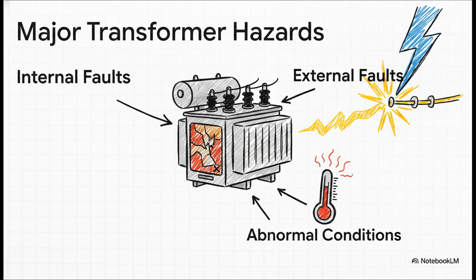First up, you've got internal faults. These are problems brewing deep inside the guts of the transformer, in its windings or its core. Then you have external faults, like a short circuit happening way down the line that sends a massive destructive surge of electricity racing back toward it. And finally, there are just abnormal conditions. You can think of this like the transformer getting a fever, maybe from too much voltage or just plain overheating. If you don't catch any of these, you're looking at fires, explosions, and, you guessed it, widespread power outages.